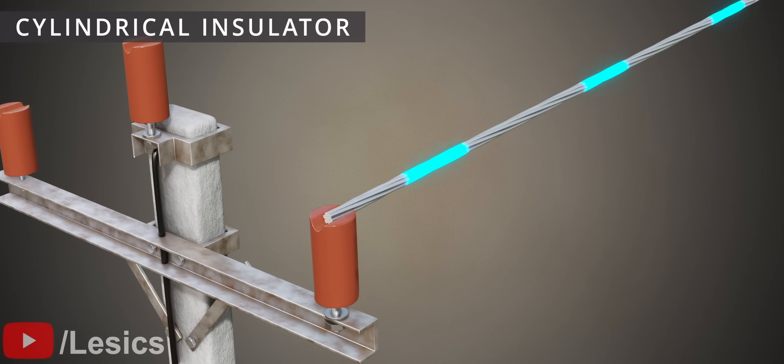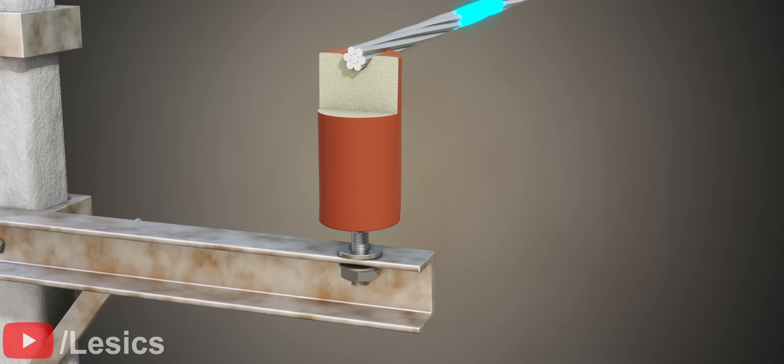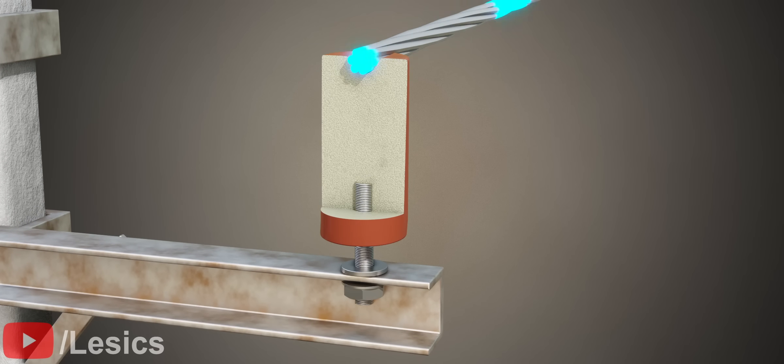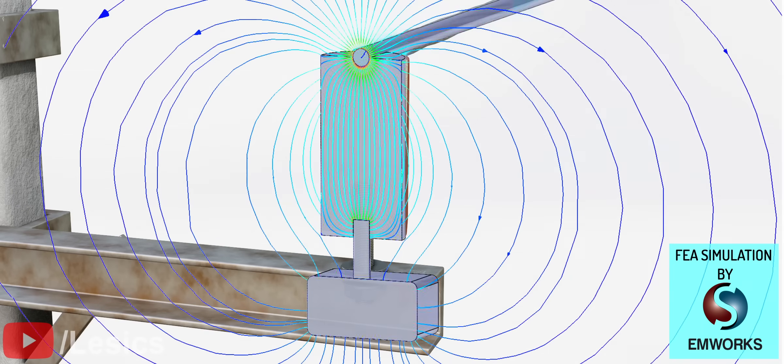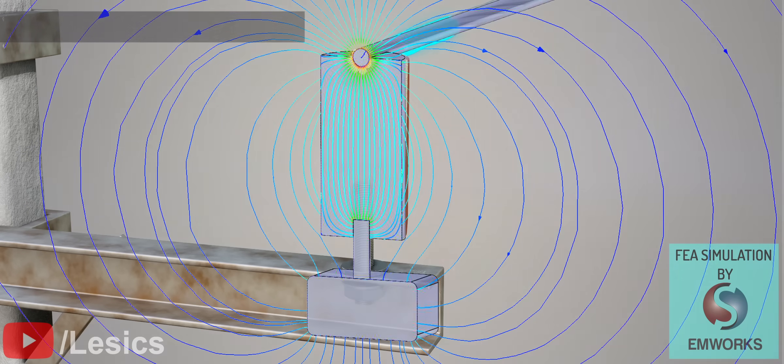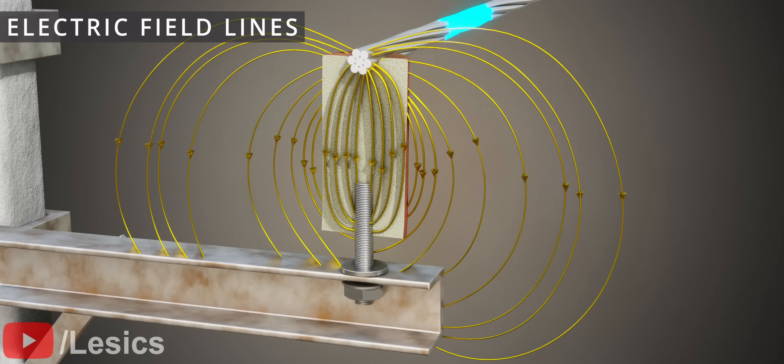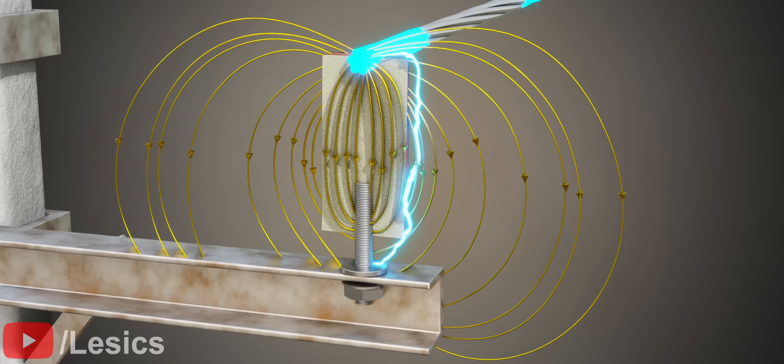However, there is a small issue. Let's study the nature of the electric field lines in this case with the help of FEA results produced by EMWorks. Here, the electric field lines pass through the insulator and air as well. You might have seen that all the electrical flashovers occur through the air. Hence, let's examine the air's electric field in detail.